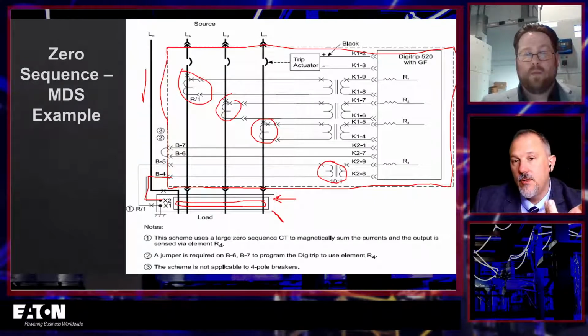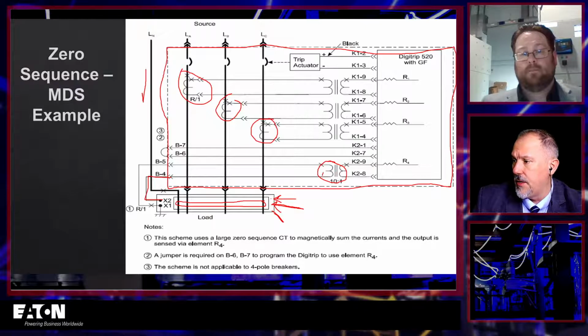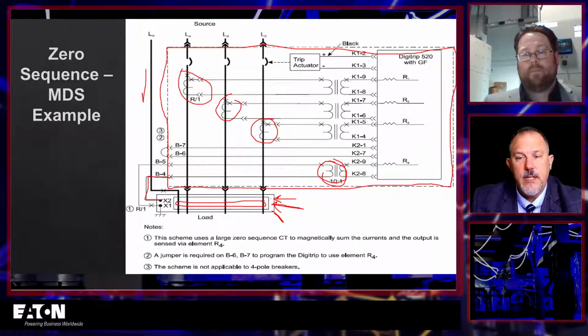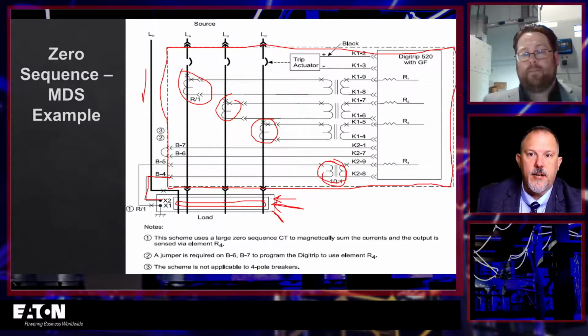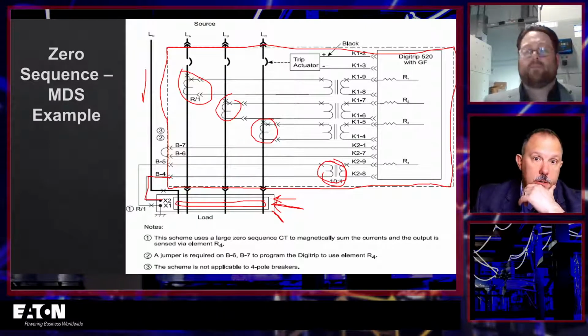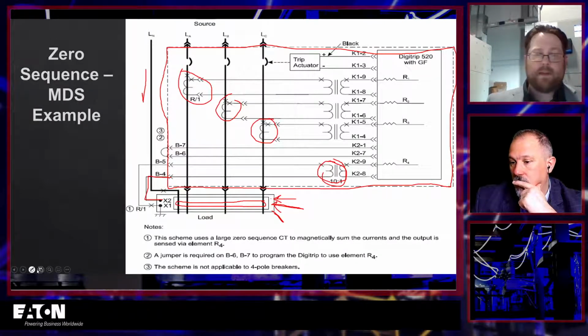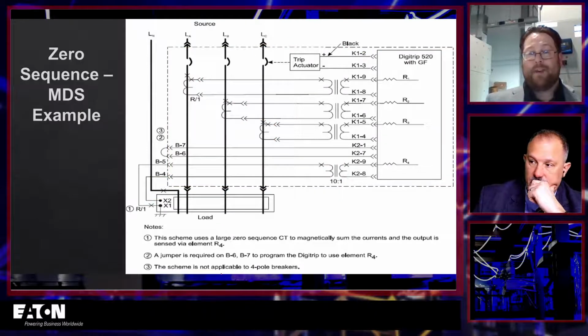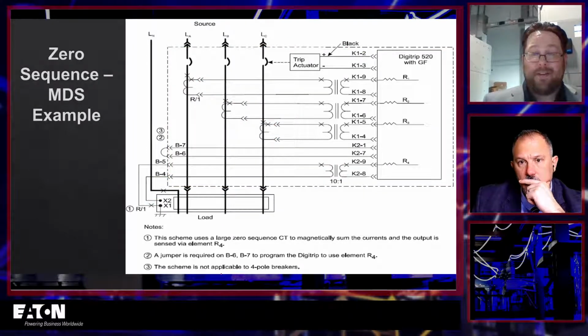And I would assume then that the size of this CT, the ratio of that CT, the accuracy of that CT is all going to be dictated by the manufacturer to tell you what you need to put there. Because if I've got another ratio over here, I've got to know. I've got to specify what CT you're going to have there, but that would probably be supplied by the gear, which if it's our gear, we would have put all this together so it would work. Right. Yeah, it's all going to be specified, as well as ensuring that you don't have CT saturation, which we already consider also.